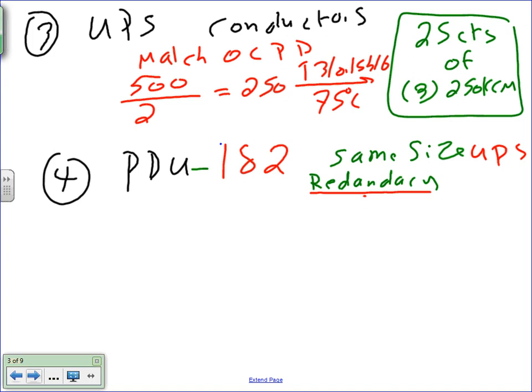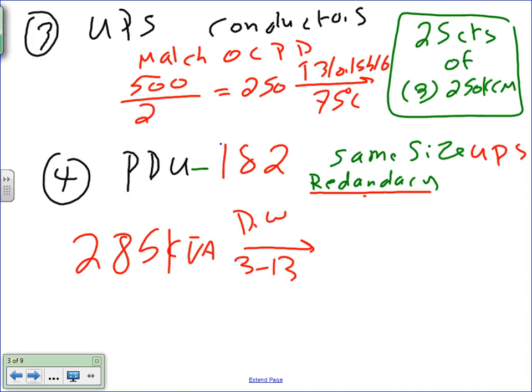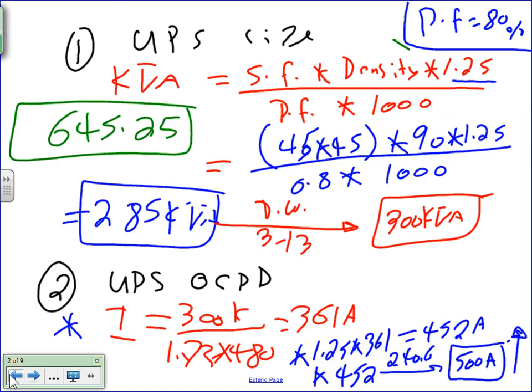So how did we size the UPS? We did all the calculation and came up to 285 kVA. I'm going to start with the same size in this case. Well, 285 kVA, and I went to the table where I asked you to put them, and came up with 300 kVA. I don't want to repeat all the steps, the same calculation. We did the same calculation like we did for the UPS, yeah? I just don't want to repeat it. When I say the same calculation, we did the same rule here. Yeah, the same size, came up with 300 kVA.